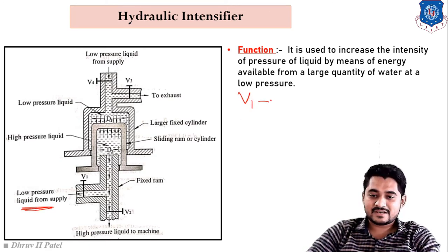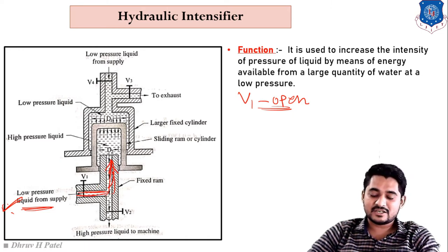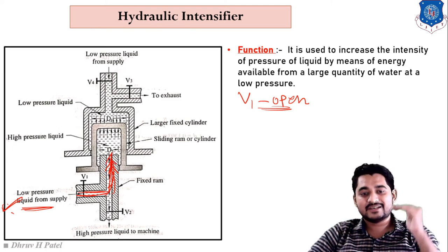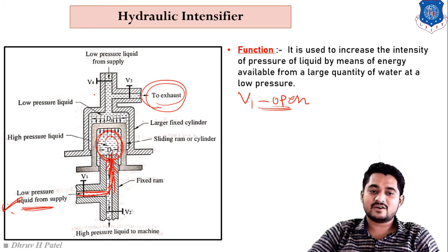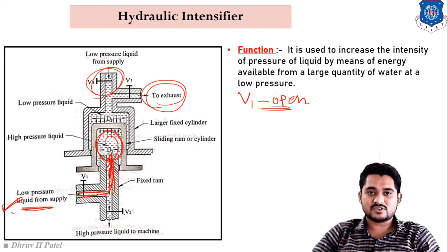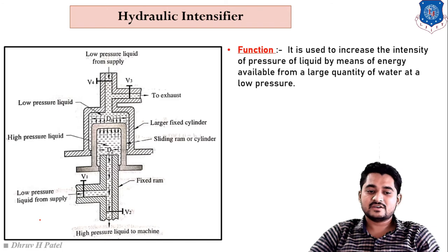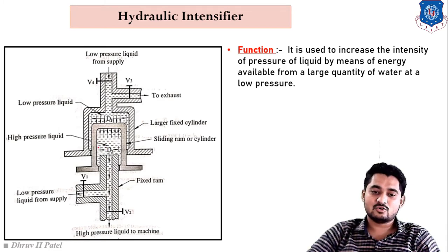First, V1 valve is opened while V2, V3, and V4 are closed. Low-pressure liquid from the supply flows into the sliding ram section, causing the sliding ram to move slowly in the upward direction. Low-pressure liquid is stored in the sliding ram section during this step.